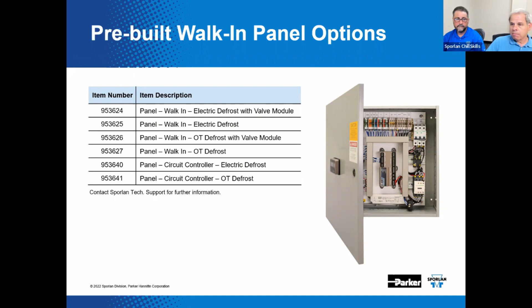Now, we have installed fuses for the relay outputs on the S3C. This includes the fans, lights, defrost, and liquid line solenoid valve. You just look under the front cover of the S3C walk-in panel. We've also included the fuse part number here as well. So underneath this cover, I think I might have said walk-in panel, I meant the cover of the case control. The control itself, yes. Case control itself. It's right there.